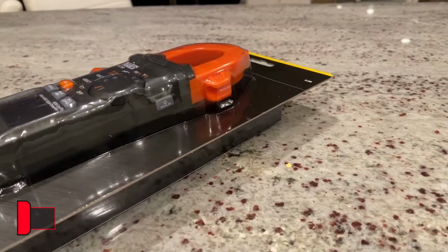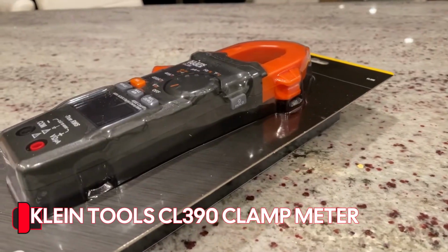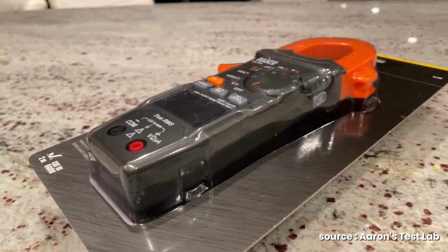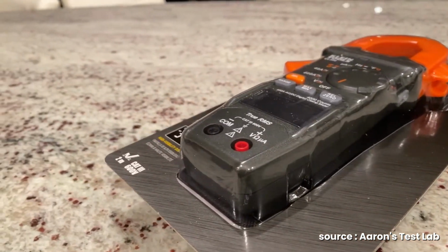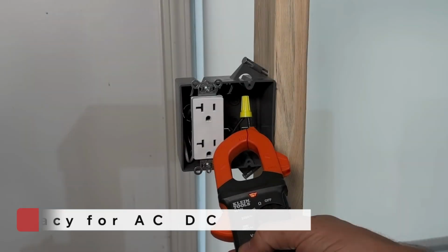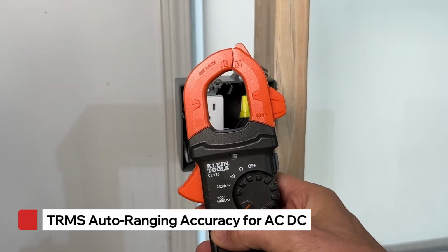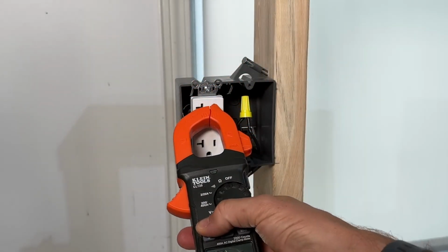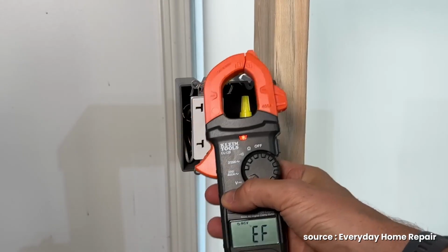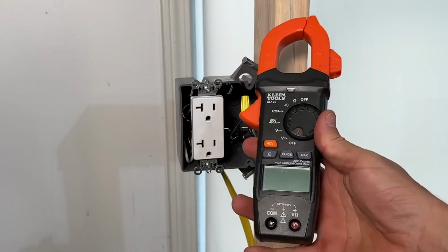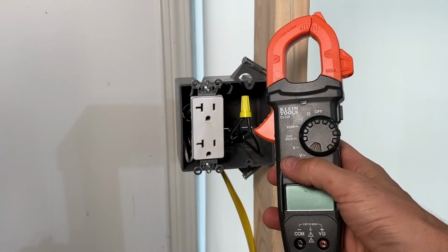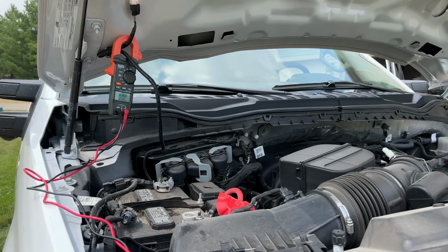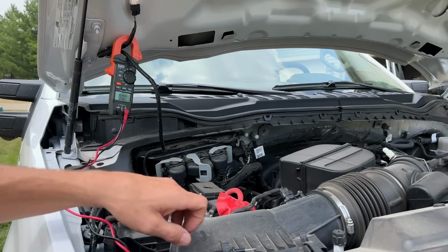First up is the Klein Tools CL390 clamp meter. Here are some advantages of the Klein Tools CL390 clamp meter. TRMS auto-ranging accuracy for AC/DC. Incorporates true root-mean squared auto-ranging technology to deliver precise measurement of AC/DC current up to 400 amperes, AC/DC voltage up to 600 volts, resistance, frequency, capacitance, DC microamps, and temperature via a thermocouple probe.